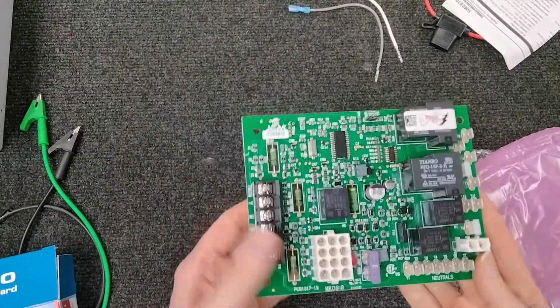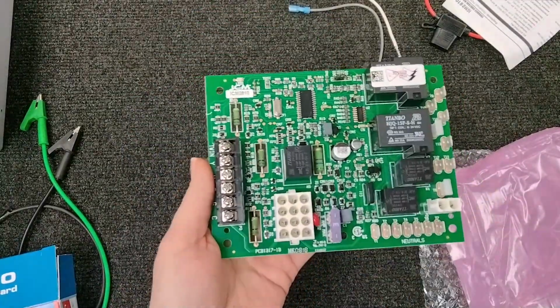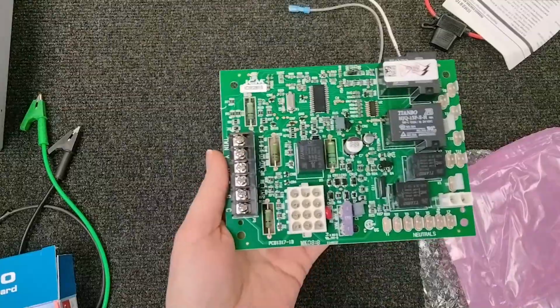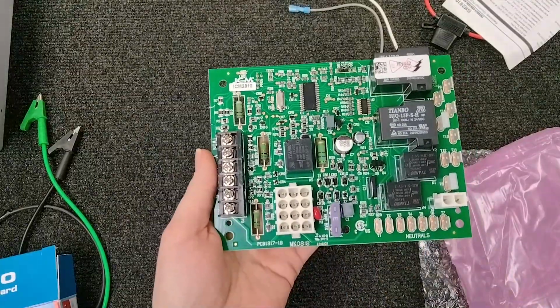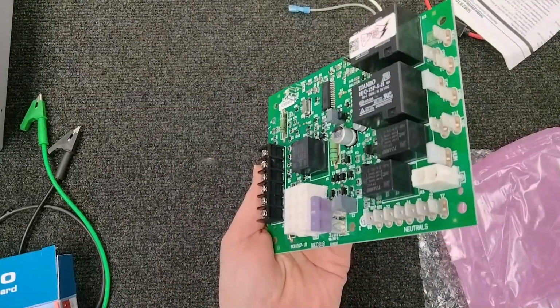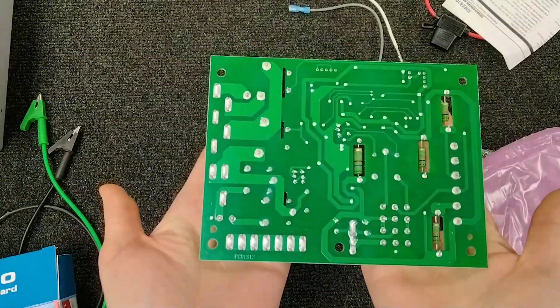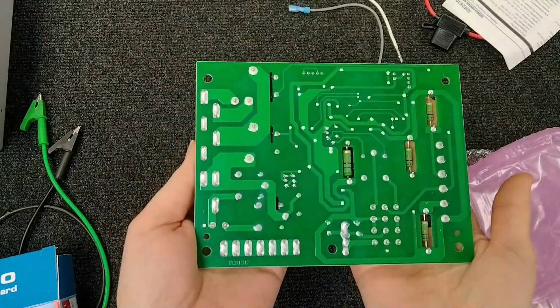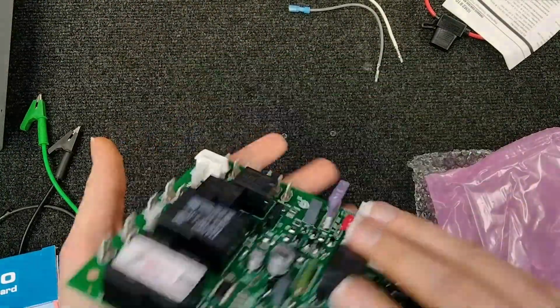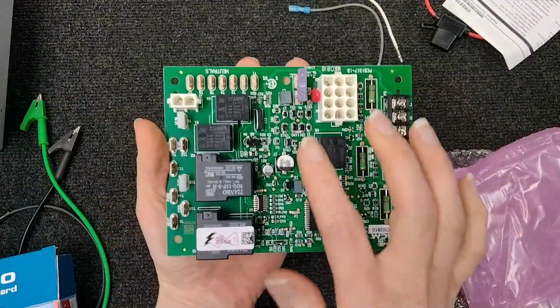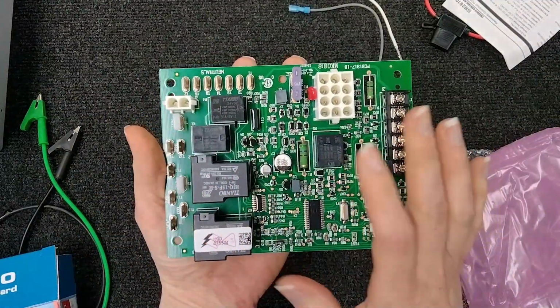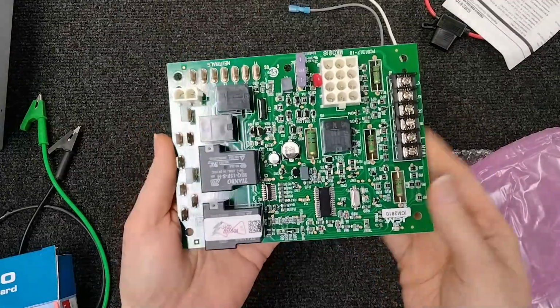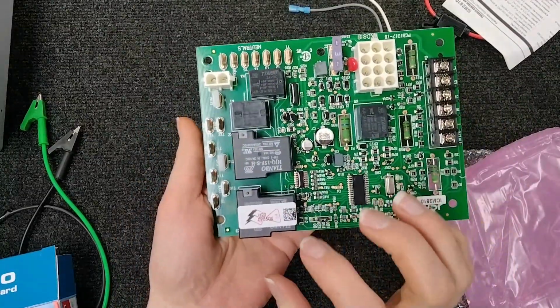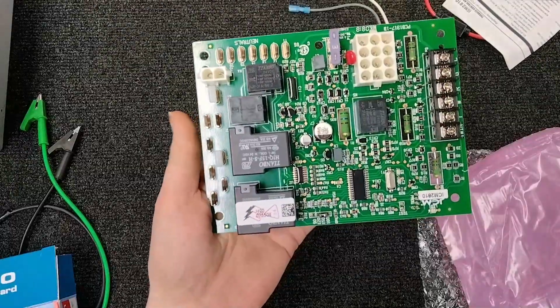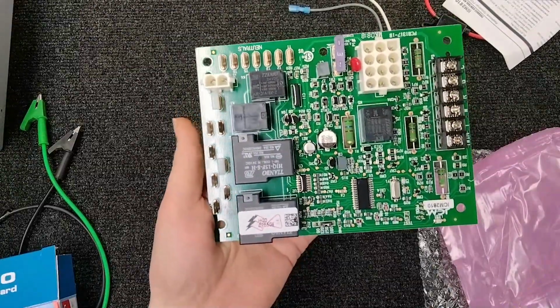So now that you know you are getting all of your power, it is sending the call, but still nothing is coming on, and your fuse is good. What you'll want to do is pull the board out of the unit. Of course, make sure that you have taken pictures of where all your wires go. Make sure that you don't forget to put those wires back, because obviously it's not going to work anyway, even if you replace it with a new control board.